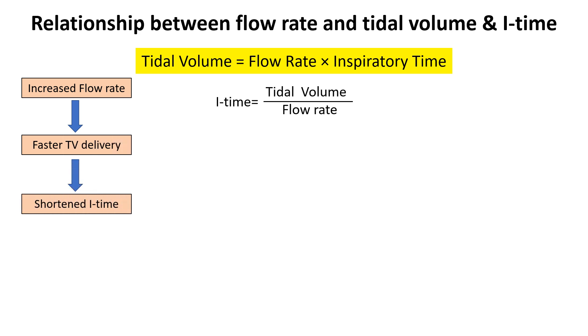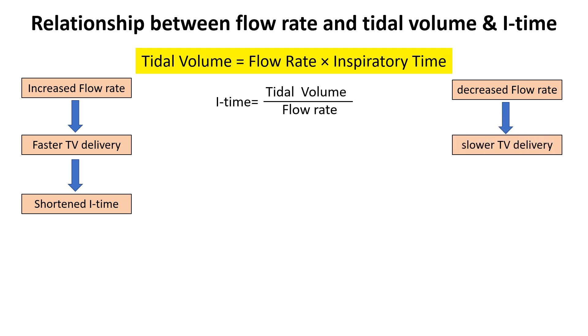If flow rate decreases, tidal volume is delivered more slowly, leading to a longer inspiratory time.